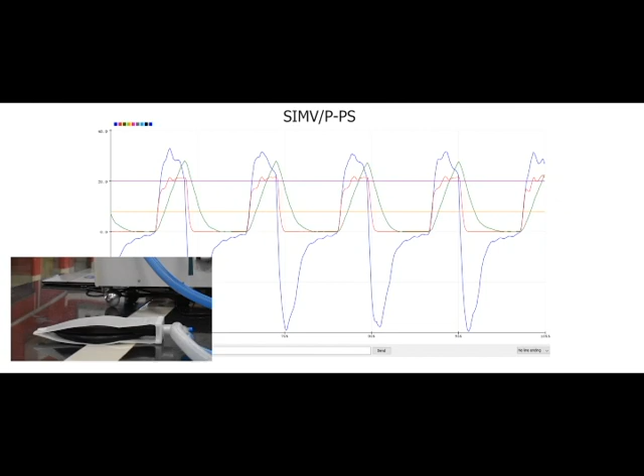Let's set the ventilator in that mode. Now you can see the test lung is actually operating in that setting, which I have just told you, which is pressure control mode of 20 centimeter of water column. It is giving the mandatory ventilation, and then whenever we have a pressure trigger, it will give you pressure support up to 8 centimeter of water column. You can see now I am giving the trigger. So it is going up to 8 centimeter of water column pressure support. And if I try to go for the time window, a small time window of 1 second we have given over here, within that, if the patient tries to take a breath, then it will support it in the ACV mode. So here I can show you a similar demonstration. You can see that it is also working in SIMV-P plus pressure support mode.